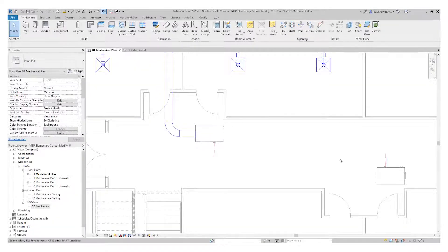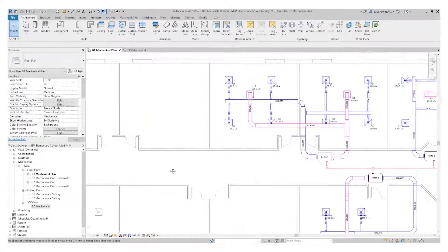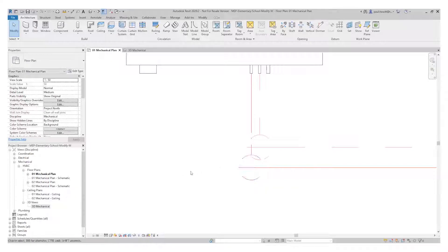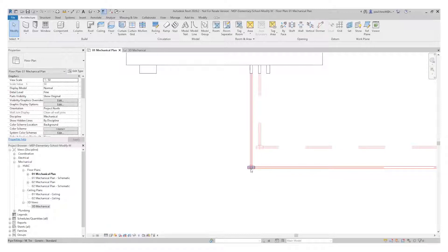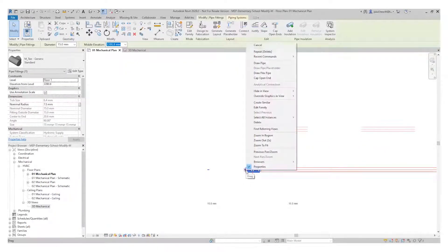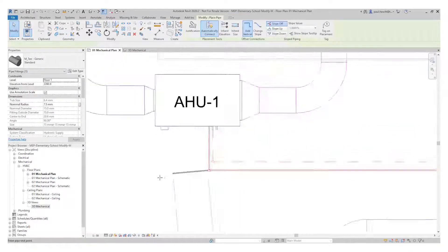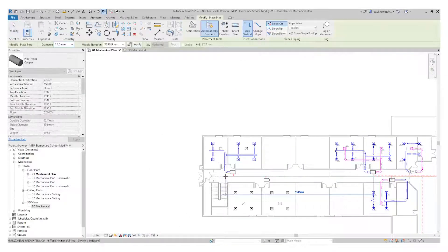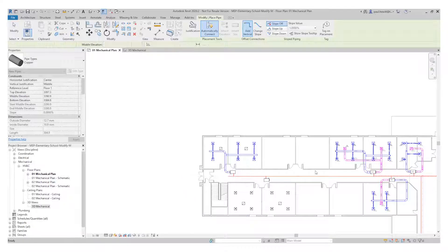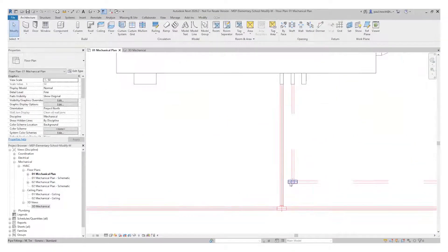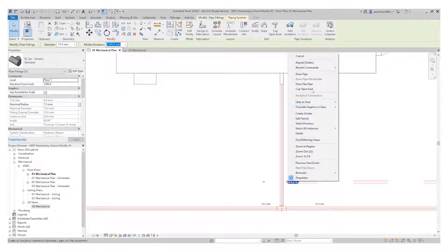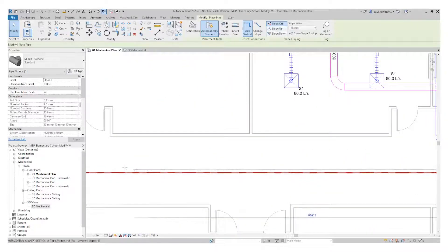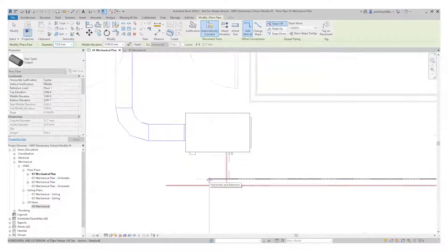So now what I need to do is go back to the existing AHUs, and let's zoom in here. I'm going to change the display to fine, so we can see a better view of the T pieces here. So I'll select one of these, right hand click on the connector, and draw a pipe. And this will just draw the pipe from that end, and I'll just go straight past that AHU unit. I'm not worried about accuracy at this point, just make sure it's straight, and do exactly the same for the return. So select the T piece, right hand click on the connector, and draw a pipe. And again, send that back down, right down to the furthest AHU unit.